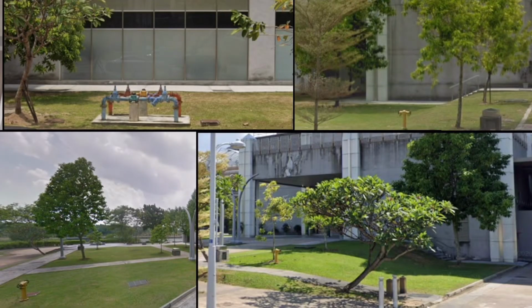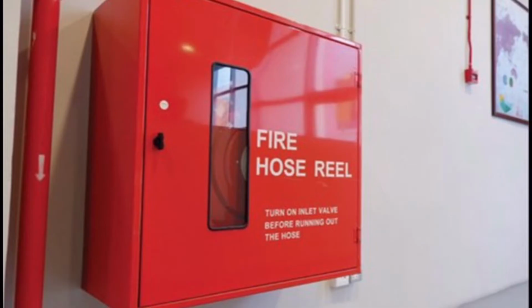The external fire hydrant is a connection point for firefighters to access the water supply during fire emergencies. These, for example, are located outside each corner, not more than 20 meters away from the building. Next is the hose reel system. It is located strategically in the building to ensure proper coverage of water to combat fire. There are 2 hose reels on each floor of the building. Each one of them is equipped with a 30-meter rubber hose that comes with a nozzle.